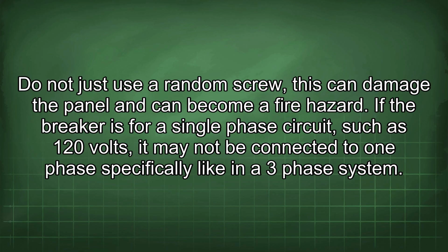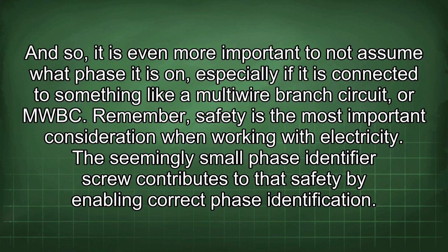If the breaker is for a single-phase circuit, such as 120 volts, it may not be connected to one phase specifically like in a three-phase system. And so, it is even more important to not assume what phase it is on, especially if it is connected to something like a multi-wire branch circuit or MWBC. Remember, safety is the most important consideration when working with electricity. The seemingly small phase identifier screw contributes to that safety by enabling correct phase identification.